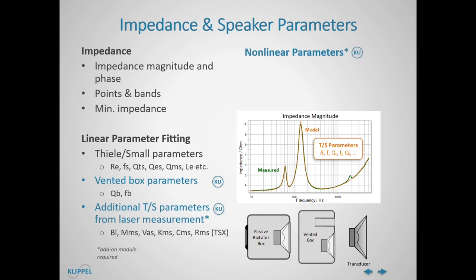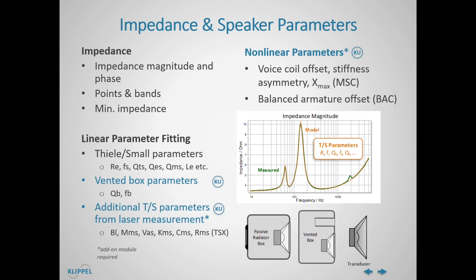Even powerful nonlinear parameters, such as voice coil offset, stiffness asymmetry, and Xmax for electrodynamic transducers, or balanced armature offset for balanced armature transducers, can be tested at the production line. This again is a unique feature of the Klippel QC.